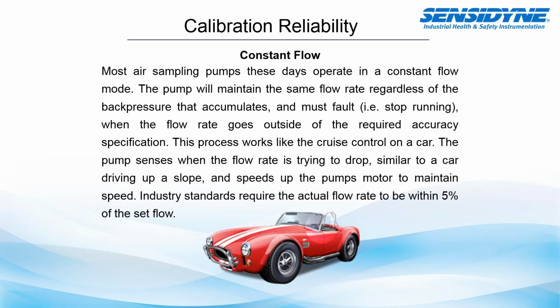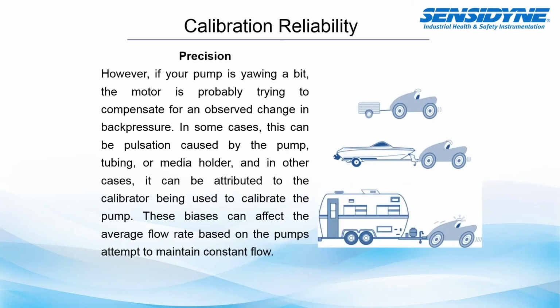Now, this process works a lot like cruise control on a car. So the pump senses when the flow rate is trying to drop, similar to a car driving up a slope, and then speeds the pump motor up to maintain that speed. So as I mentioned, industry standard requires that the actual flow rate be within plus or minus 5% of that set flow rate.